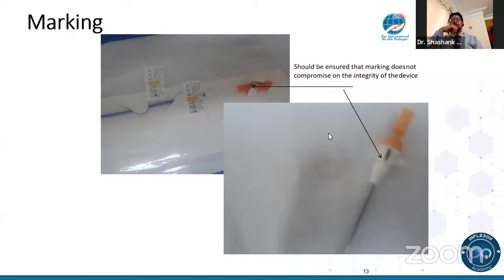In the case of cardiac catheters, which are usually the ones in India that are reused a lot, we could look at something called sterilization marking tapes, which are also available. These are small rolls of tape which come in different colors, and can be put around an area very similar to this. As you can see, the cursor is being moved around by Dr. Soma. You can see that these are the areas that can be marked, or can be put with a small sterilization tape. The good thing about these tapes is that they allow the sterilant to penetrate, they maintain the sterility of the device, and they do not get erased very easily. So this is something that you can also look at.